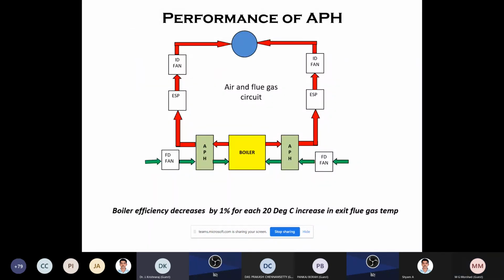Now the air preheater system. If you go to the air preheater system, there is a boiler. The hot flue gas is going here, going to the ESP, ID fan, and then it is coming out from the chimney. From the fan, air is sucked from the atmosphere, it is going to the air preheater, air is getting heated up and going to the boiler. So the air preheater is the main place where the heat exchange takes place. The exit flue gas temperature will lose the heat and the same heat is going to the air. After that it will go here. Likewise, if there is some problem, if proper heat exchange is not taking place, automatically what will happen?